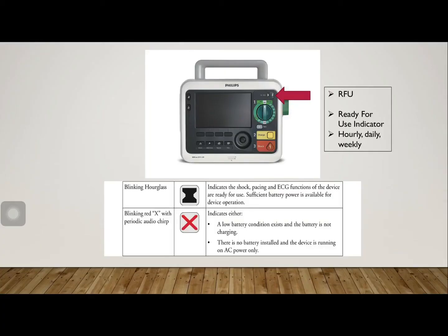So that is our RFU or ready for use indicator. If it is a blinking hourglass, it means it passed its hourly, daily, and weekly internal self-test. So you can really guarantee that the machine is okay and always ready to go. If it is a blinking red or has an X mark, the minor troubleshooting is to check if the battery is in the battery compartment. If the battery is there, then maybe the battery is depleted. So just charge it for about 15 to 30 minutes. If it still shows an X even after charging for about 15 to 30 minutes, then you should perform the run-off check.